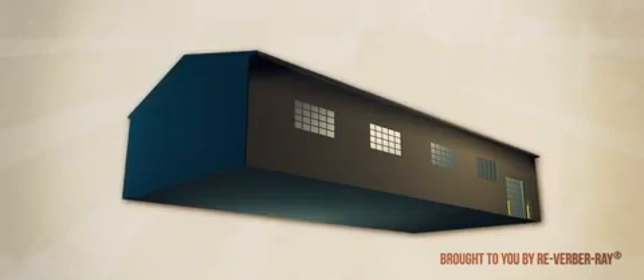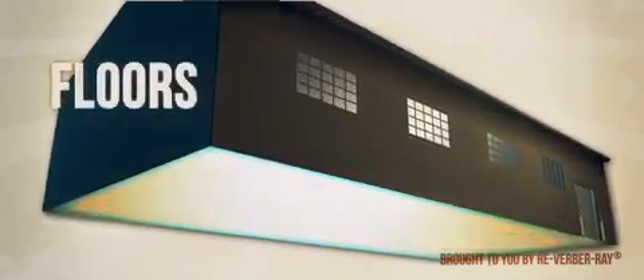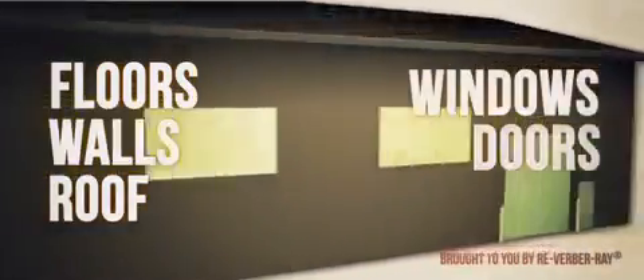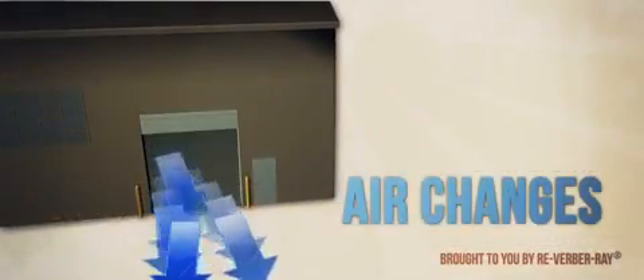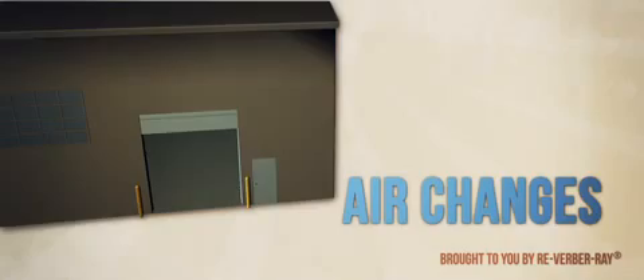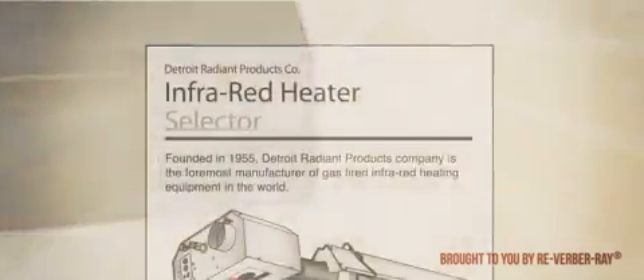To begin, a formal heat load calculation must be conducted. Factors to include are floor and wall area, windows and doors, and air changes. This will most accurately provide the necessary BTU heat load requirements.